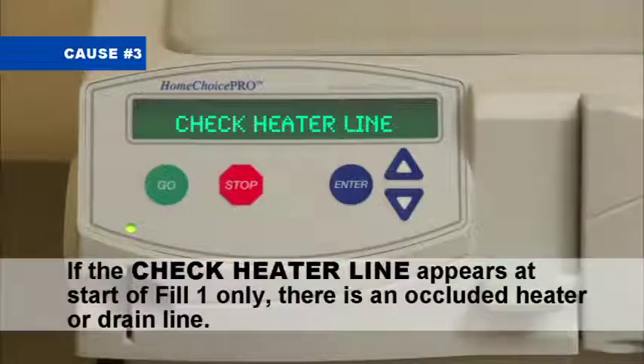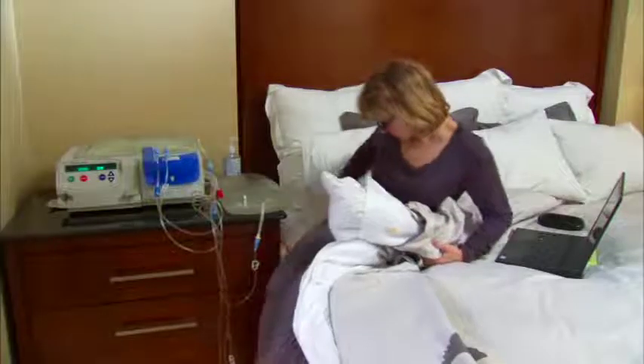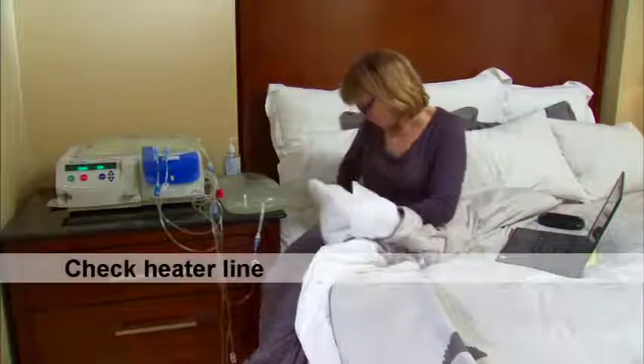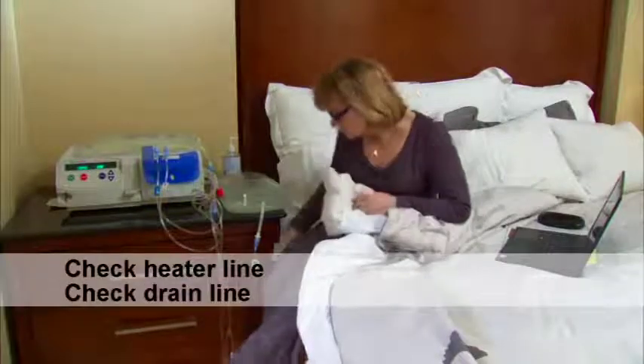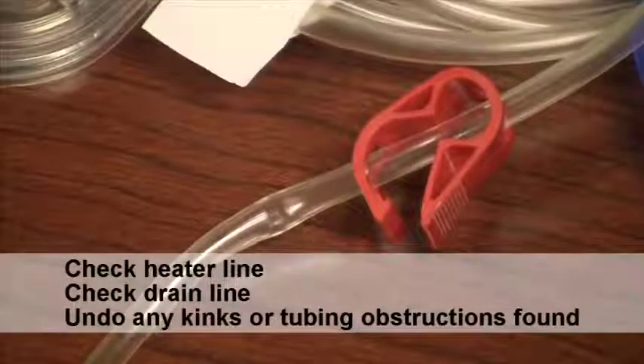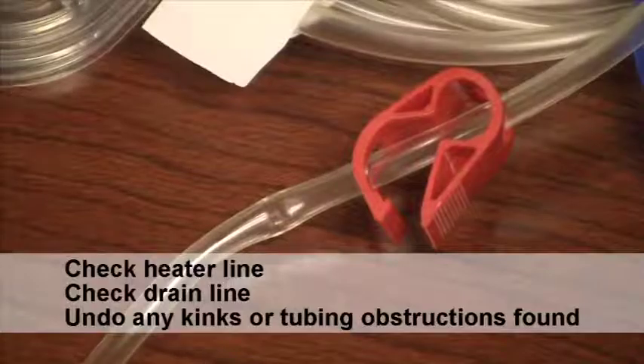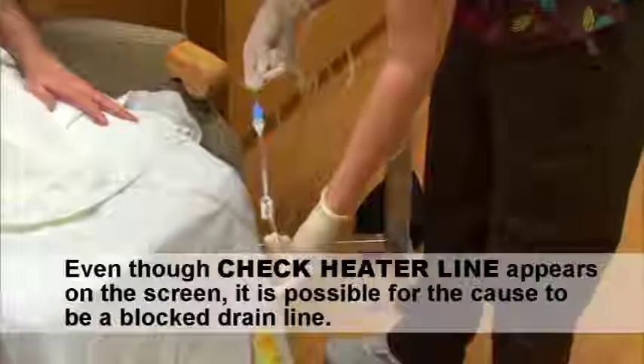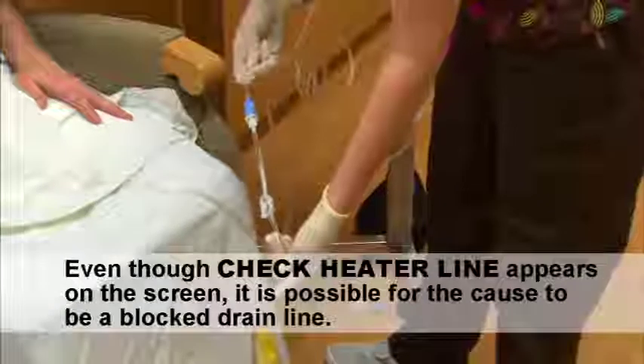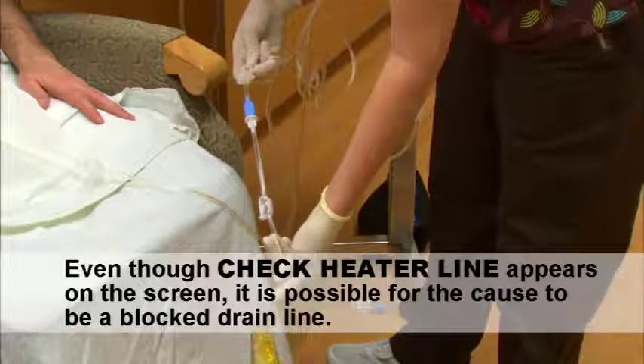Cause number 3. If the check heater line appears at the start of fill 1 only, there is an occluded heater or drain line. If cause number 3 occurs, check the heater line, check the drain line. Undo any kinks or tubing obstructions found. Even though check heater line appears on the screen, it is possible for the cause to be a blocked drain line.